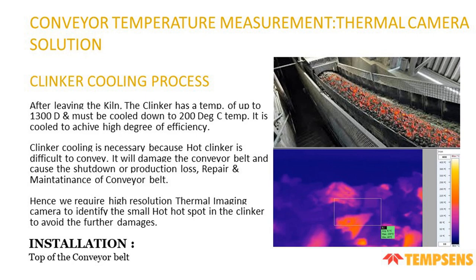Clinker cooler process. After leaving the kiln, the clinker has a temperature of up to 1300 degrees and must be cooled down to 200 degrees temperature. It is cooled to achieve a high degree of efficiency. Clinker cooling is necessary because hot clinker is difficult to convey. It will damage the conveyor belt and cause shutdown, production losses, and repair and maintenance of the conveyor belt. Hence, we require a high resolution thermal imaging camera to identify small hot spots in the clinker to avoid further damage. Installation: top of the conveyor. The picture shows the conveyor temperature and the ROI made.